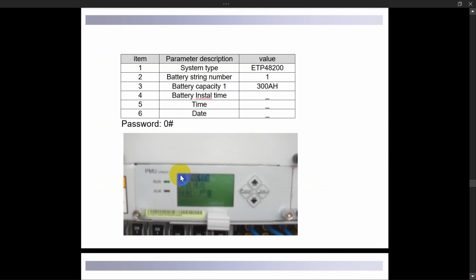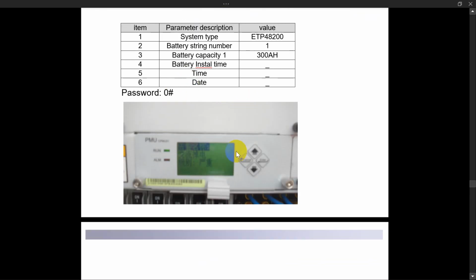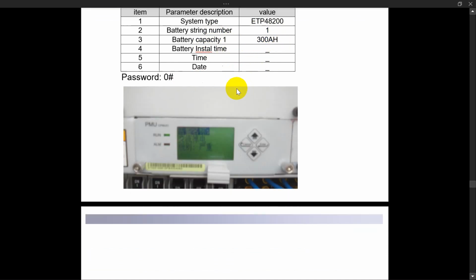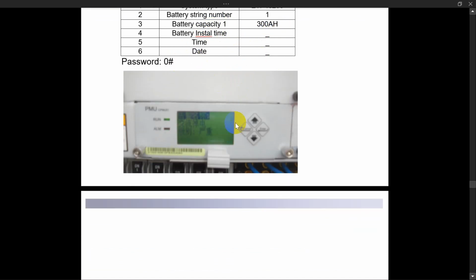Here in any sub rack there is a controller. In the controller we adjust the configuration according to our operator scenario or standard. Like what you will do for the battery string number, it's according to the site, 1 or 2. Also battery capacity, the same 300 ampere, and other specifications according to operator scenario and approval.